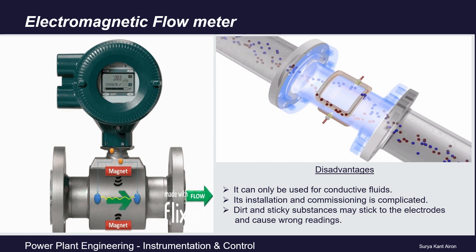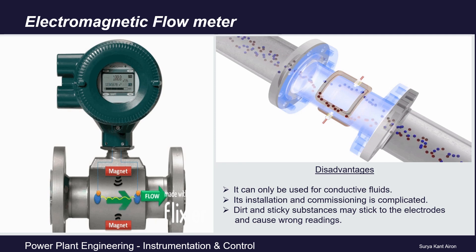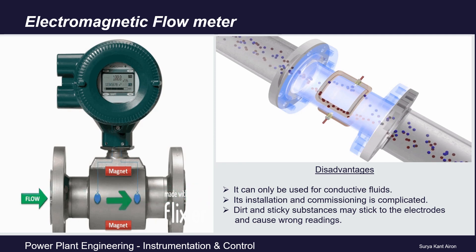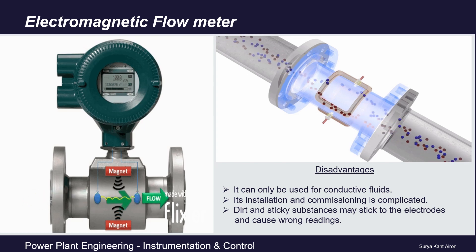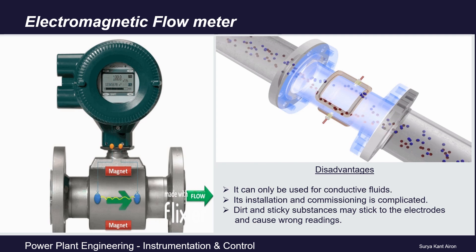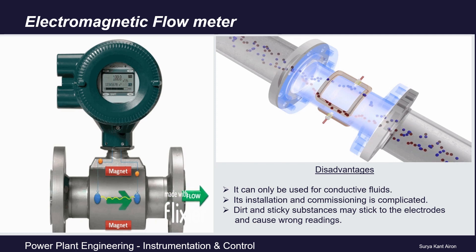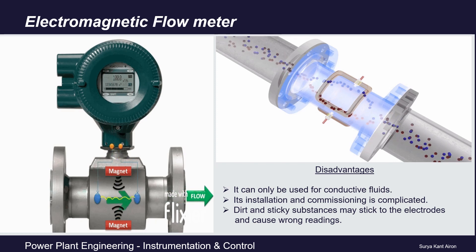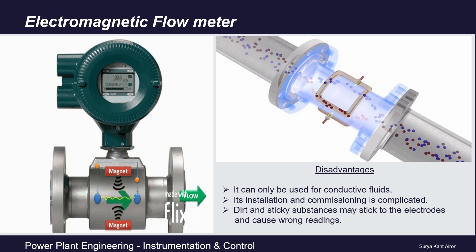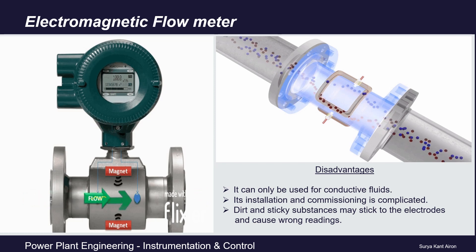At the DCS, it is advisable to compensate the received volumetric reading with temperature and pressure. Each instrument in the field is calibrated under certain operating pressure and temperature reference conditions, which can be checked from its calibration certificate. The actual temperature and pressure of the pipelines are also measured, and the raw flow measurement is compensated for temperature and pressure variations with respect to calibrated reference values.